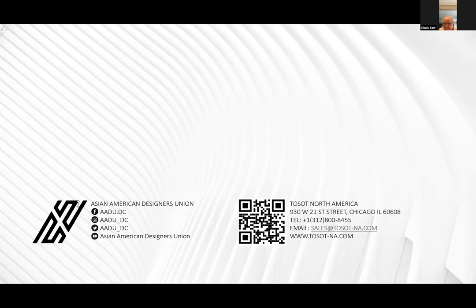Thank you. More about multi-split systems - when you have hundreds of indoor devices like the Charter Court project, how is per-unit condensation handled in these VRF installations? With an IDU, an indoor unit, you have to offer condensate drainage. The simplest way is gravity, but if you're not able to do gravity, there are multiple different types of condensate pumps available.